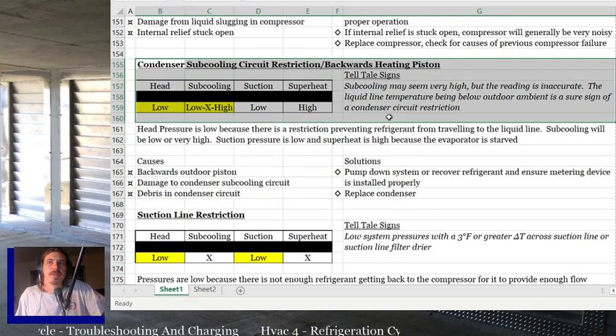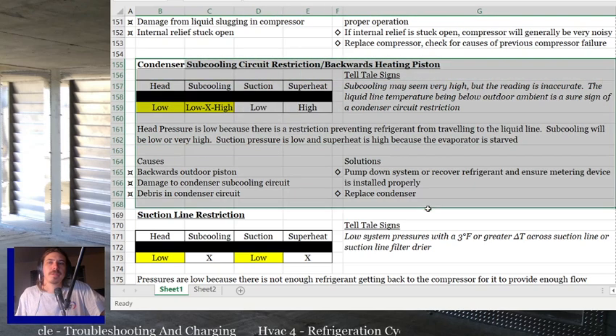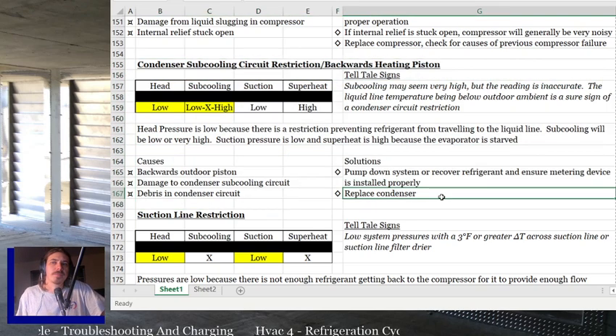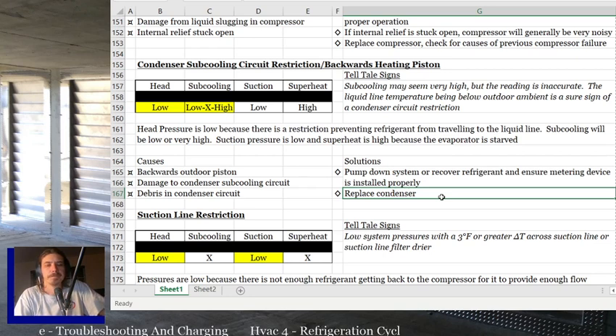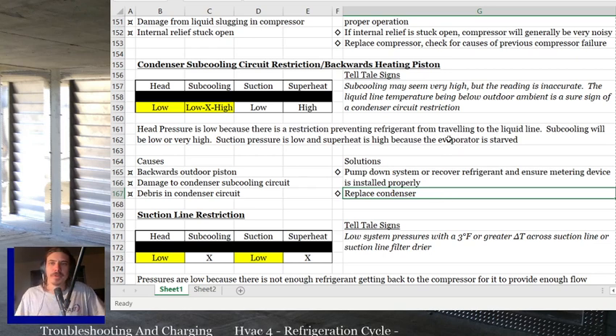But generally, when you see this issue, it's usually going to be something to do with either the valves exiting the condenser, the metering device for heating, or somebody put a big old dent in that condenser, and it'll probably be hard to miss.